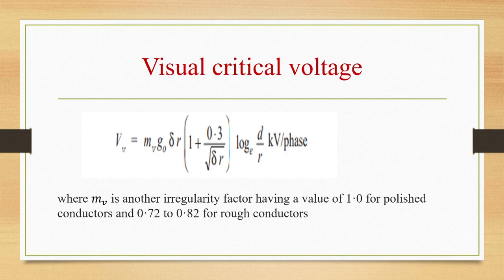So what is visual critical voltage? Visual critical voltage is the minimum phase neutral voltage at which corona glow will appear all along the line conductors, and in case of parallel conductors, corona glow does not begin at the disruptive voltage Vc but appears at some other higher voltage Vv, that is called the visual critical voltage. So the phase neutral effective value of visual critical voltage is given by Vv is equal to mv g naught delta R into 1 plus 0.3 by root delta R log d by R base e kilovolt per phase.